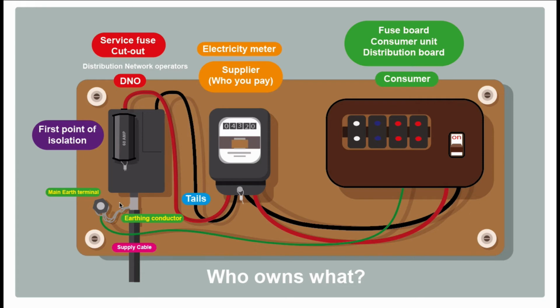If you wanted to move the cutout, you'd have to call the DNO, and they'd come and have a look and give a quote for the job. They wouldn't actually move this at all. They wouldn't want to try and shift this cable. Like I said before, this cable is very old and it's unsafe to move. They'd probably just cut this supply off, bring a new supply in from the street. Generally what they do is put a box outside now. So you'd have your cutout in the box outside. You'd run your tails into the house for your fuse board and your meter. So yeah, we can move the fuse board, but nothing else.